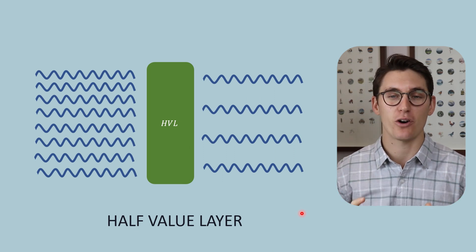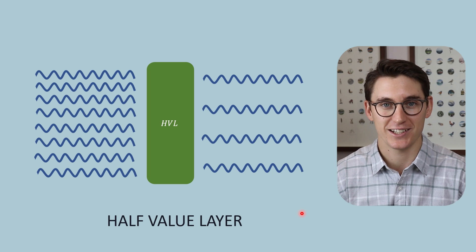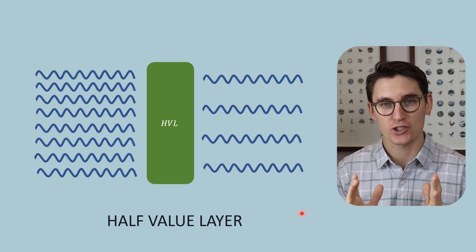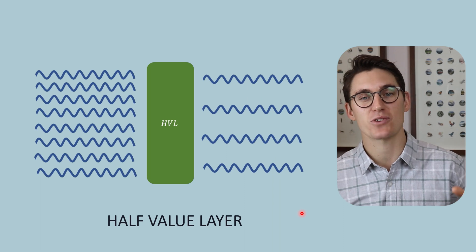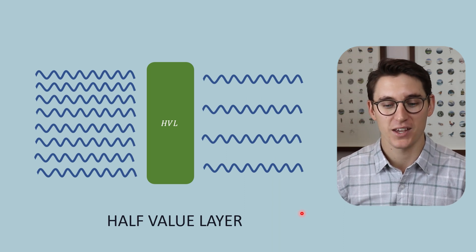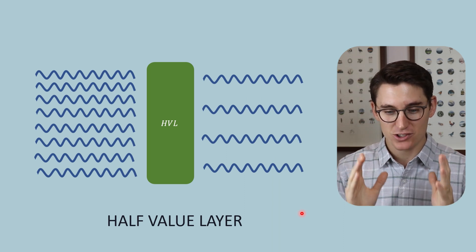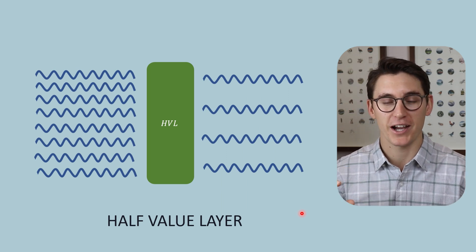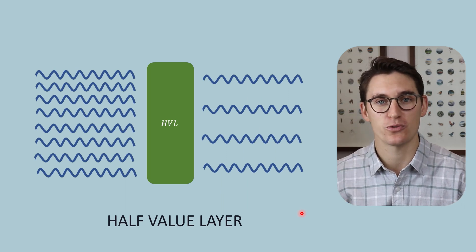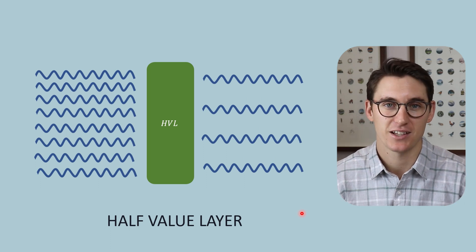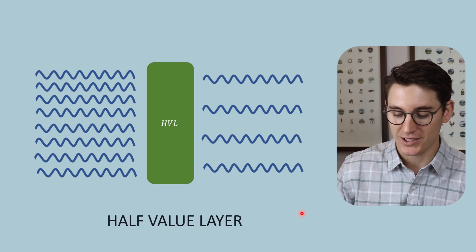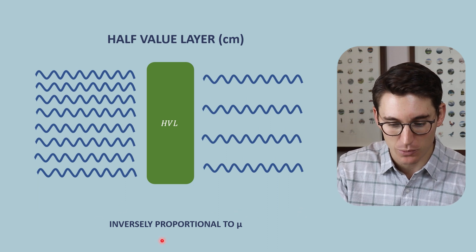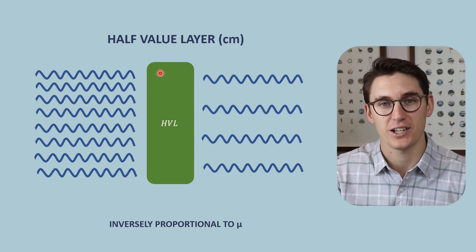Today we're going to be looking at the half value layer. In its most simplest terms, the half value layer is the thickness of tissue required to reduce the x-ray beam intensity by half. It's the thickness of tissue that will reduce the photon number of the x-ray beam by half — removing half of those photons over that distance. We saw that the half value layer is inversely proportional to our linear attenuation coefficient.